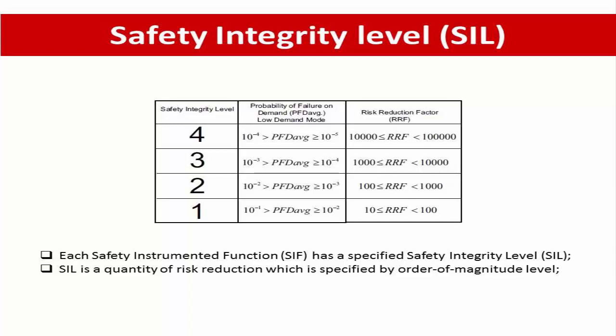When existing protection layers are insufficient, adding a SIS protection layer will be required. The quantity of risk reduction is specified by order-of-magnitude levels called Safety Integrity Levels, or SIL, as indicated in the table below. SIL levels range from one to four, defined by the magnitude of the probability of failure on demand or risk reduction factor.